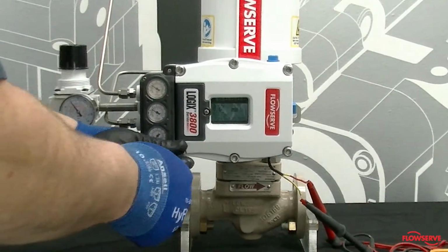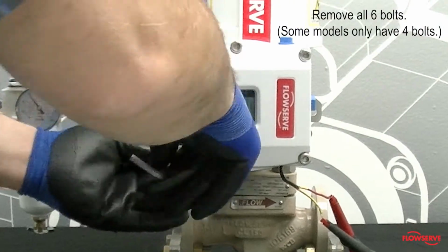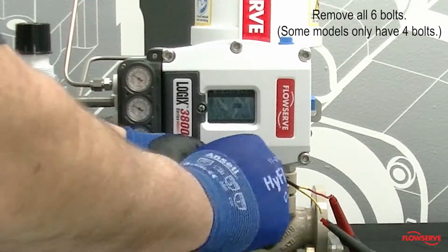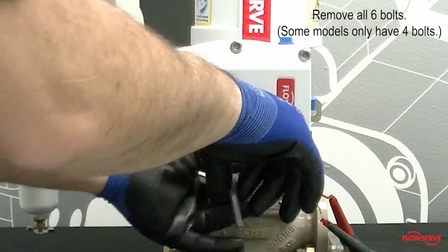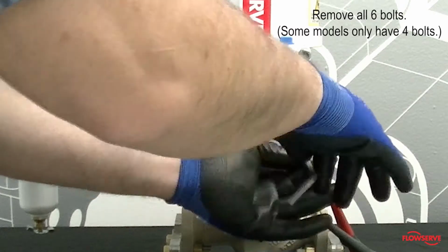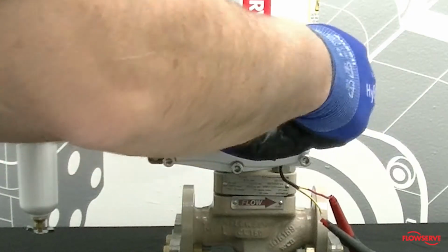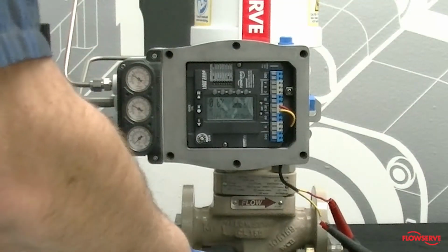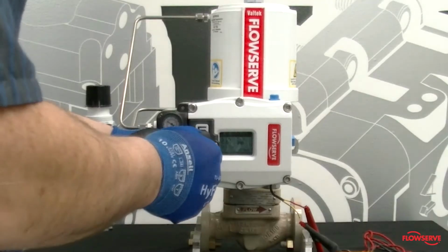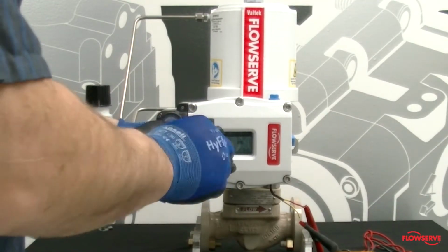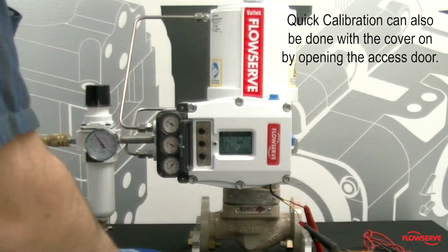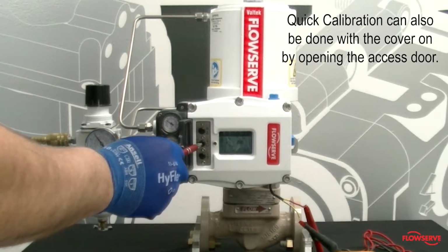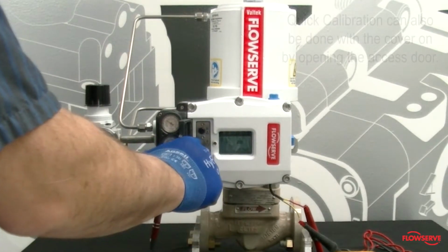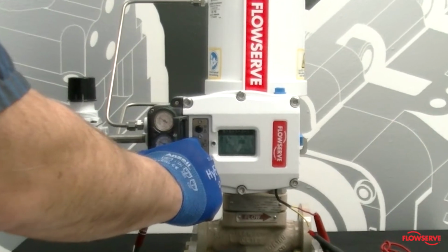Remove the 6 outer housing bolts to access the quick calibration button and dip switch internal configuration. Note that some models only have 4 bolts. If you are not setting the dip switches at this time, there is an alternate quick access door that can also be used. Next, start the calibration by pressing and holding the Quick Cal button for at least 3 seconds.